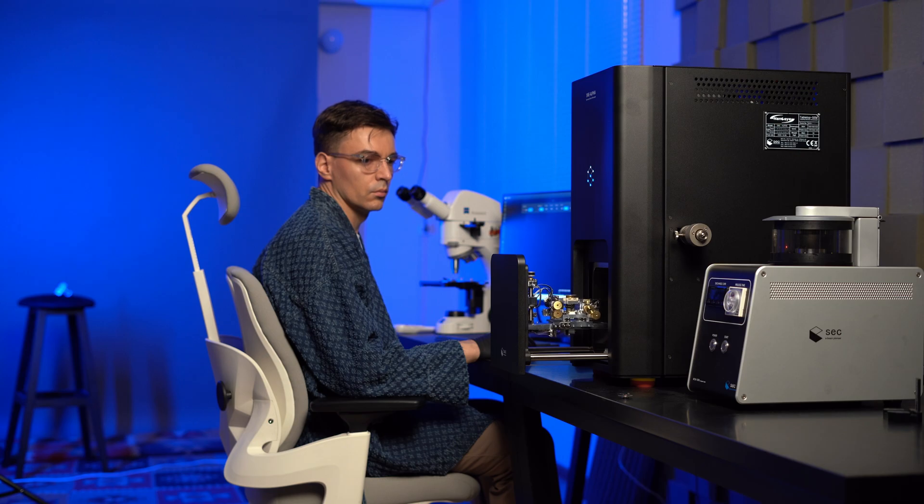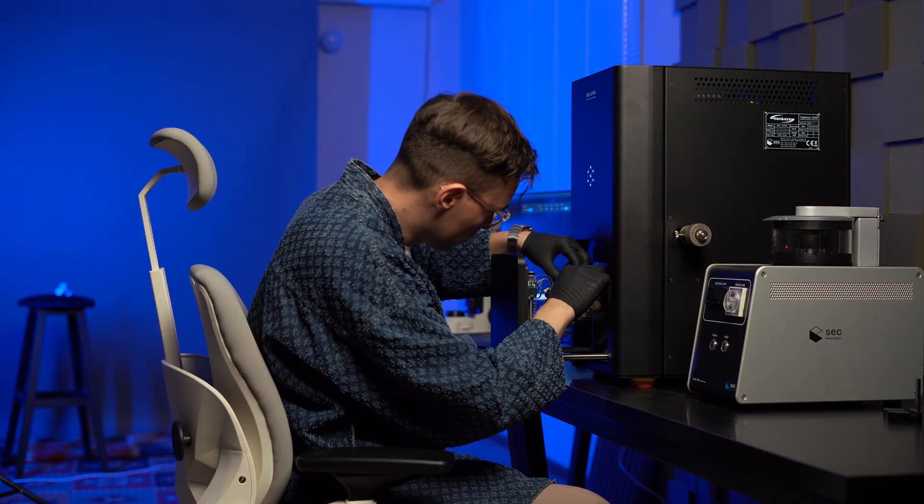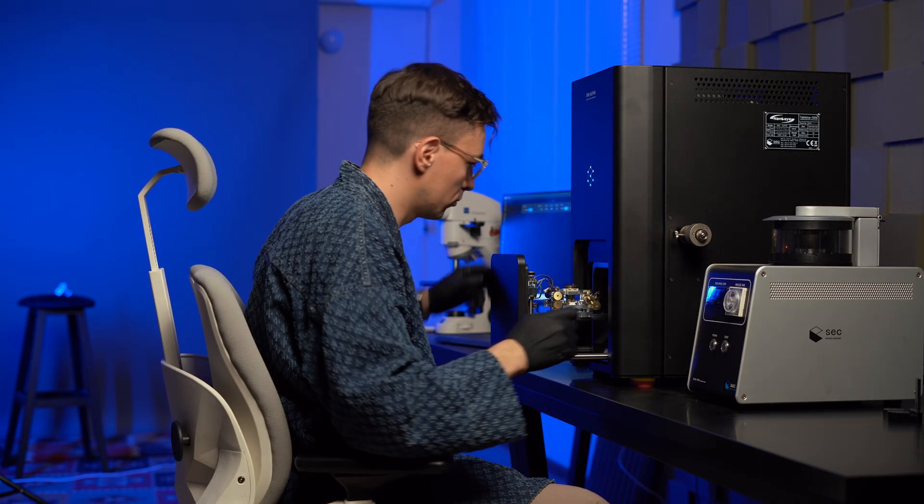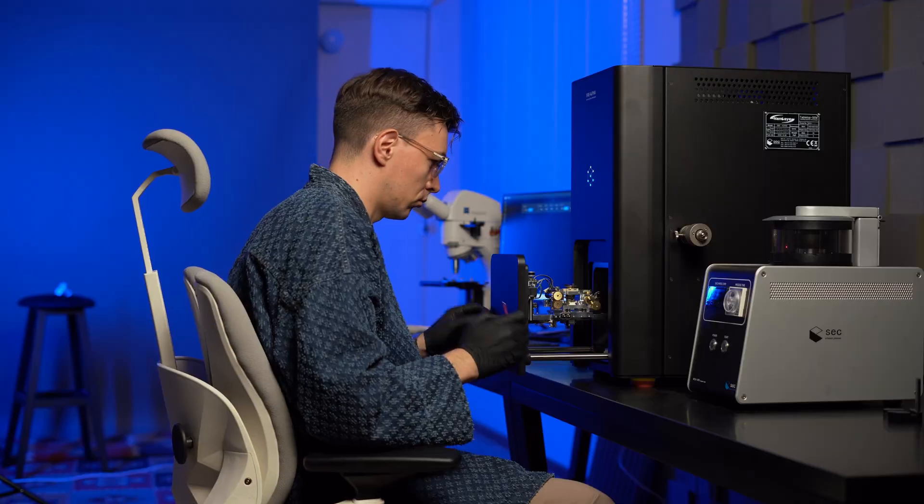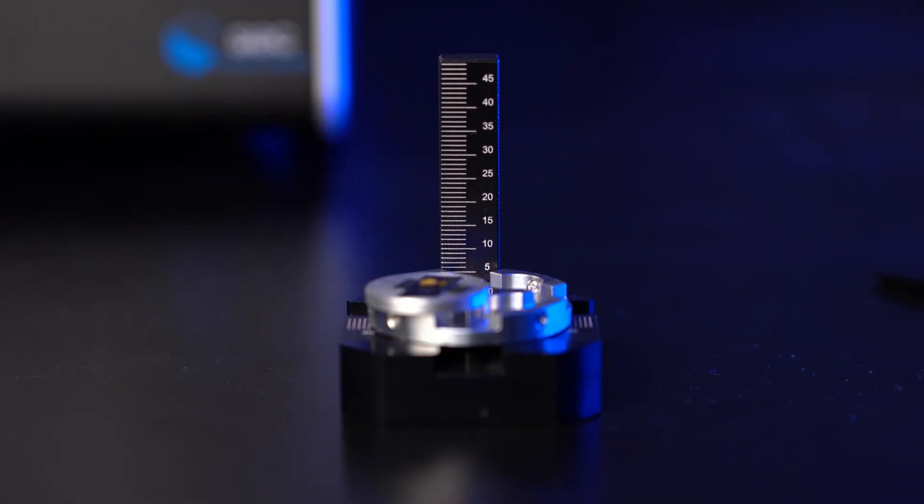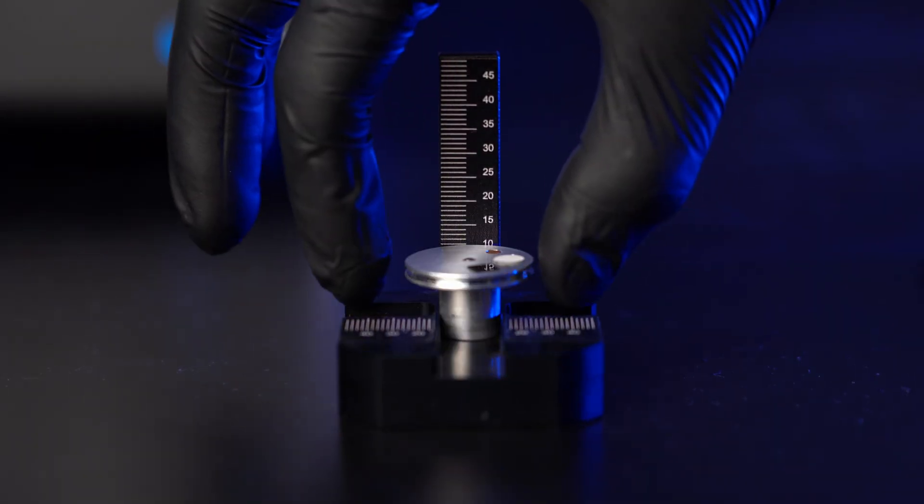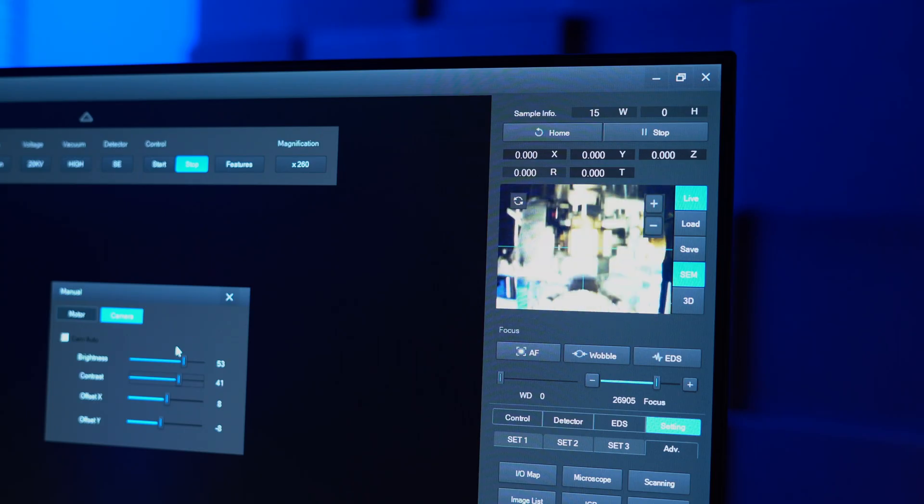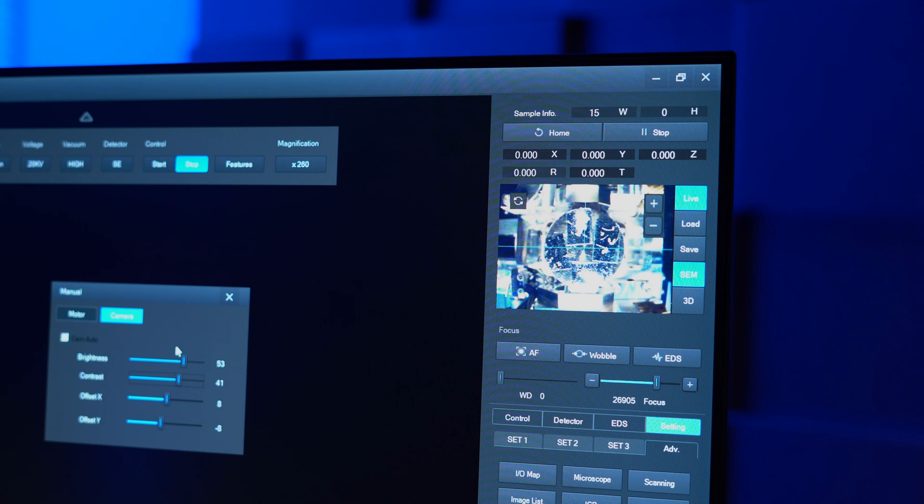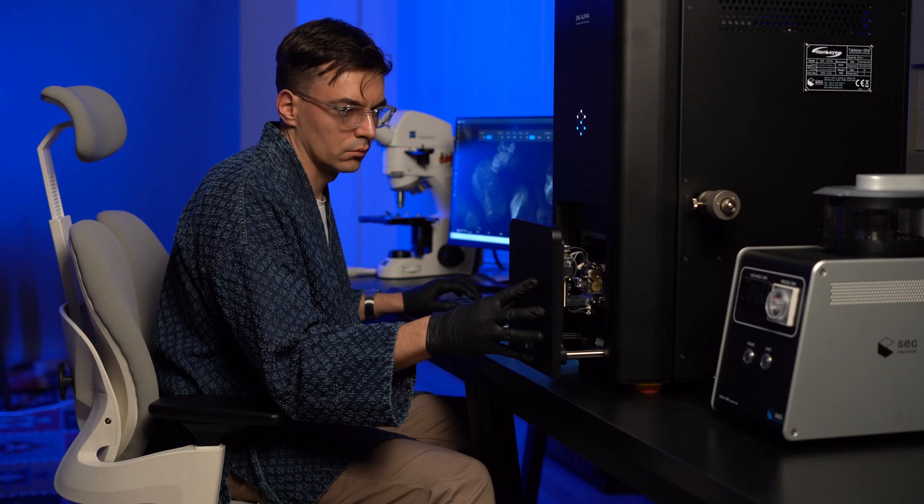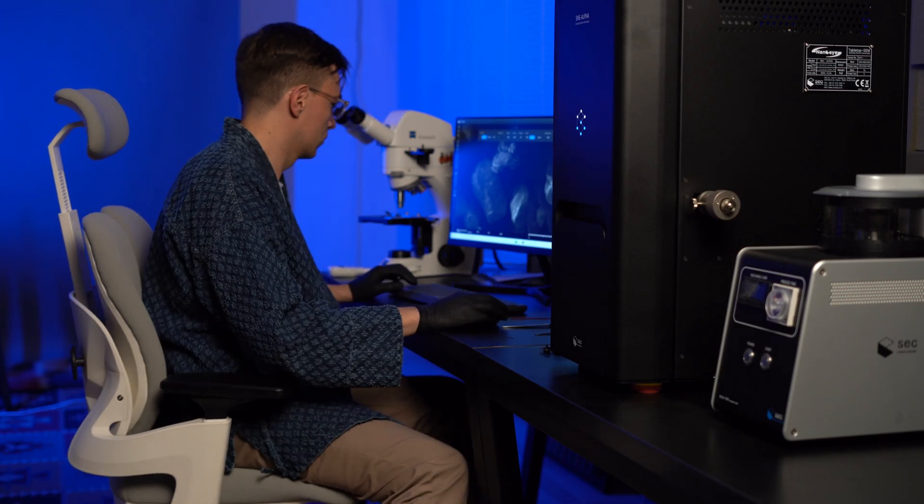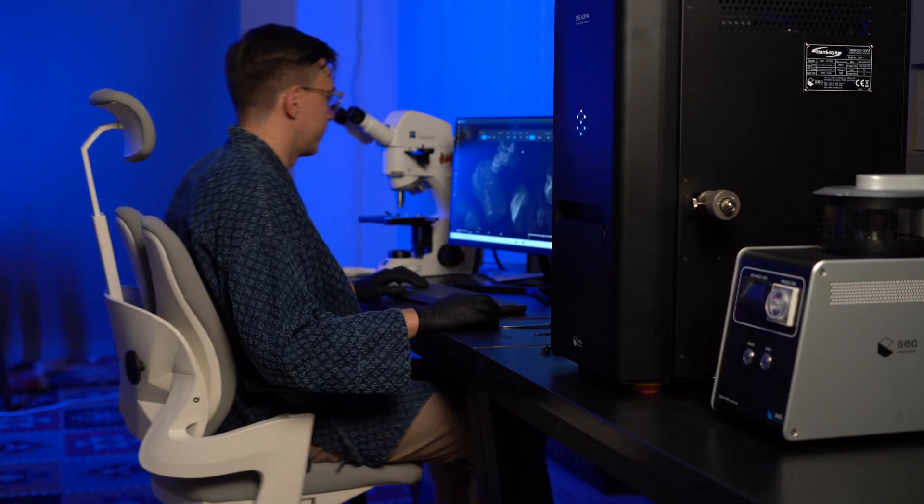We need to perform stage align and mount this tab on the microscope stage. We have a special caliper gauge to measure the size of the mounted sample. And we need to type this data to the software, just to avoid collision between the sample and the detectors. Navigation camera is a useful option and it helps us with XY positioning. Okay, we're ready to go. Let's close the chamber and initialize vacuum.